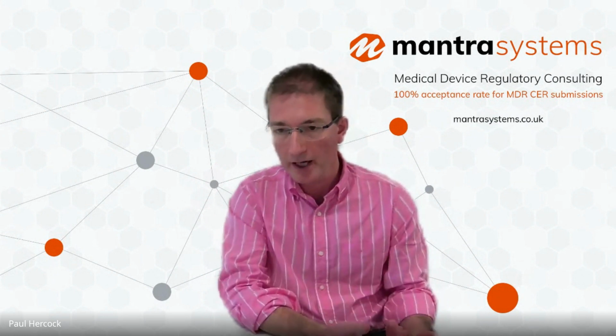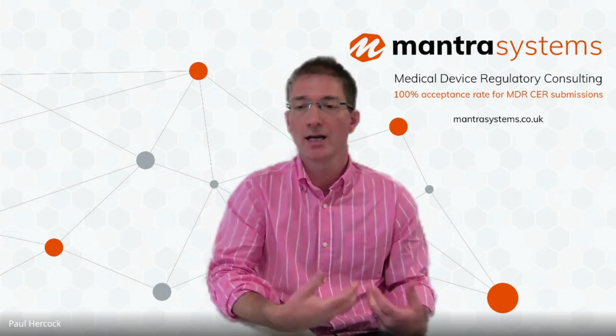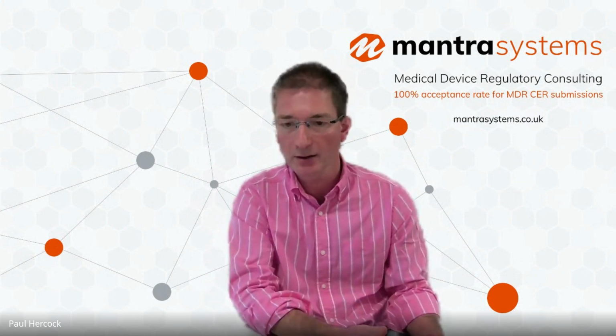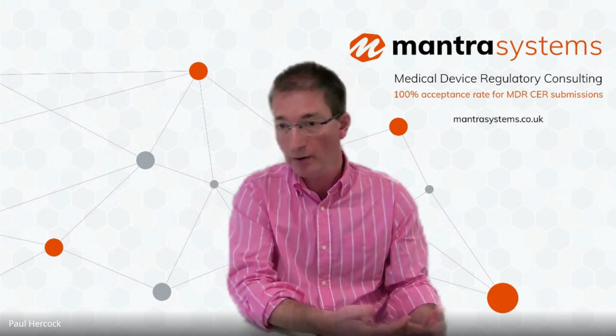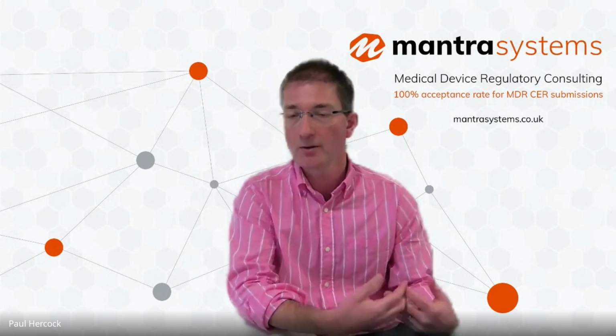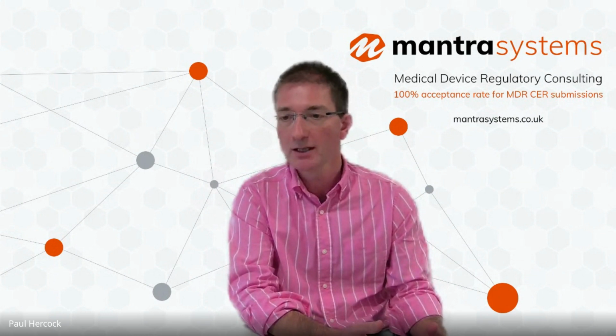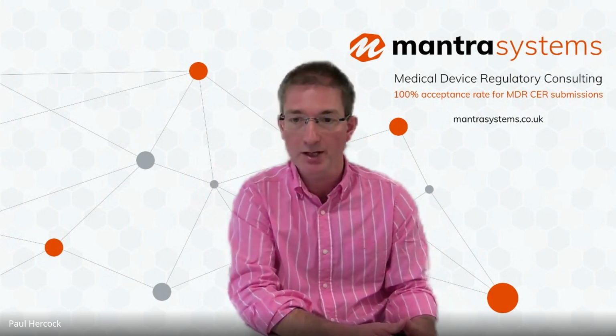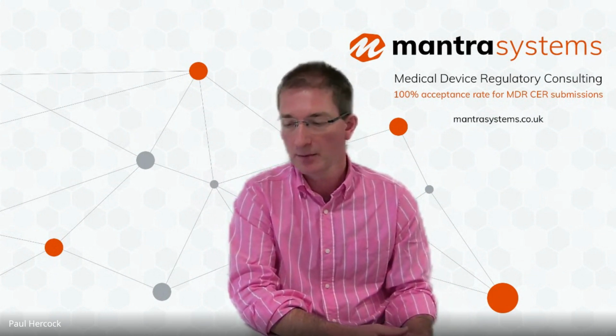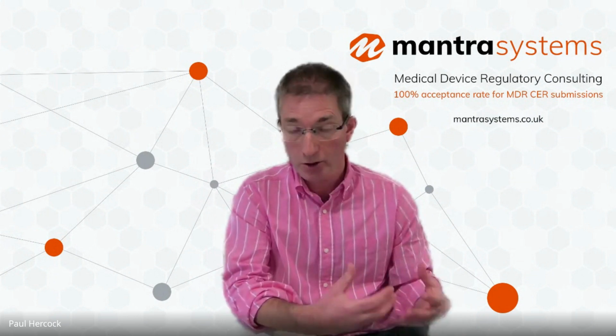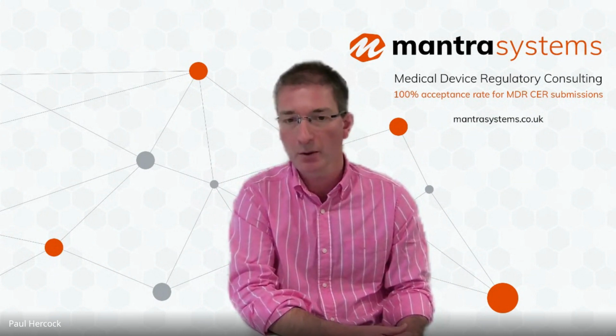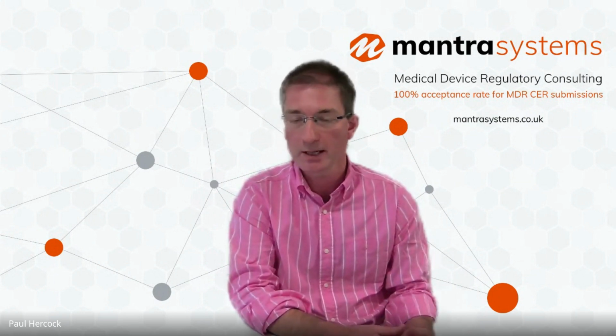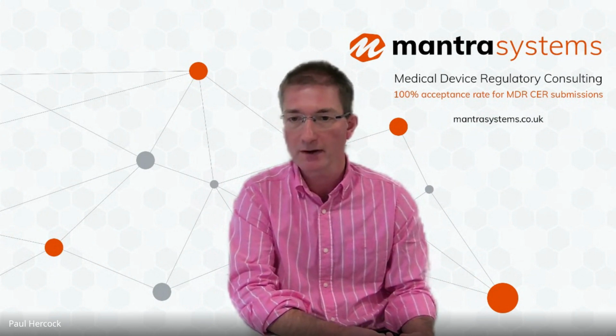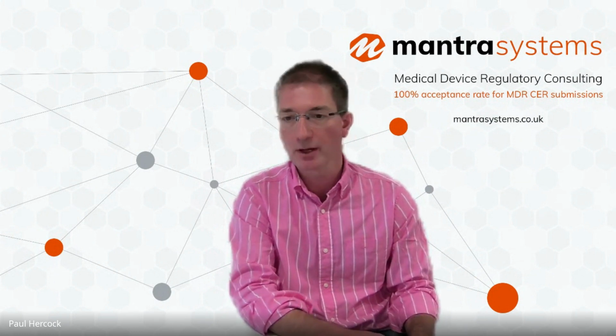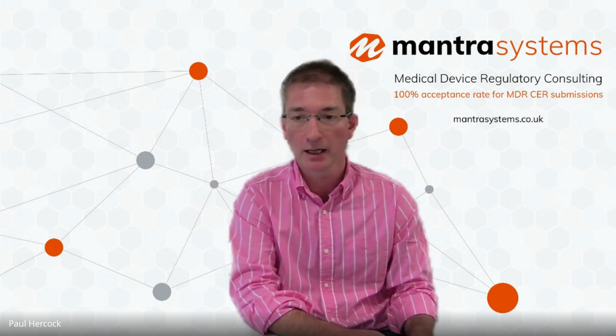And it's not that there can't be any differences, it's that there needs to be a scientific rationale for why those differences won't affect safety or performance. So they don't need to be identical, but you need to be able to justify the non-significance of any differences. And then at the end, you form a conclusion, which ideally should show alignment with the requirements. And the best source is MDCG 2020-5, which sets out the MDR requirements really for equivalence.